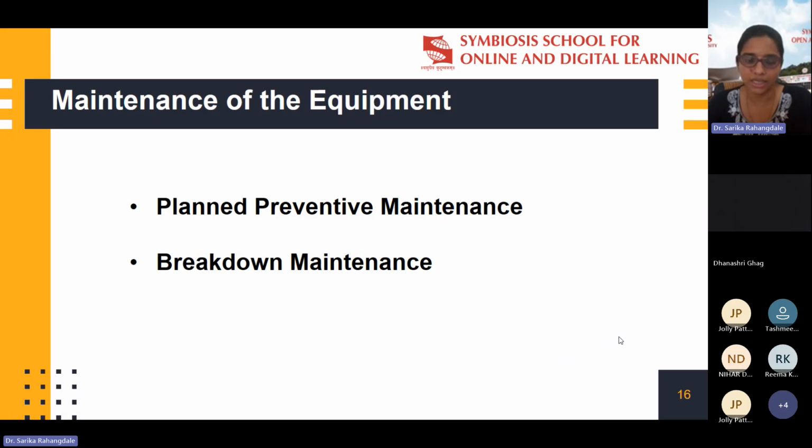Planned maintenance is decided based on how frequently maintenance is required for that equipment, so that it will not be out of service and remains in continuous service of the community. This planned maintenance is usually scheduled at specific intervals. The procedure and the intervals are usually established by the manufacturer. You have to record how frequently maintenance is done, and document everything in the maintenance register.